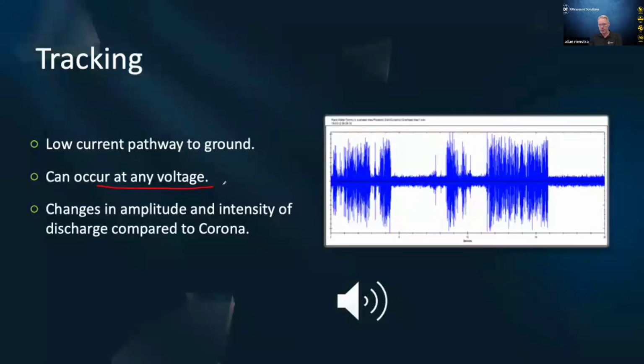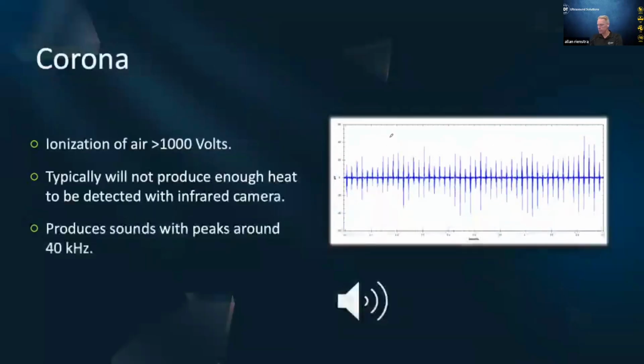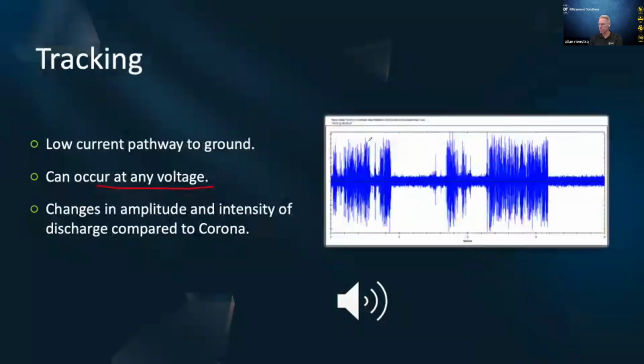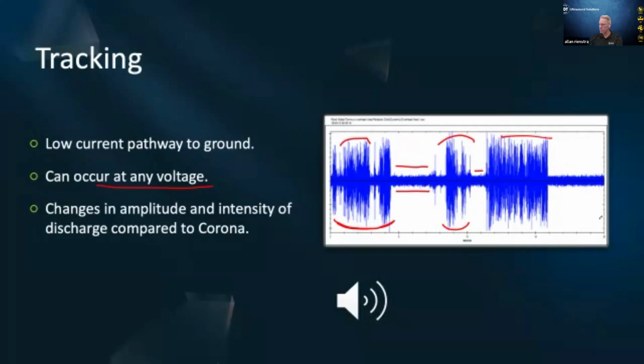The difference between, if we just flip back to the corona, you'll see these repetitive peaks, and they have a repetition frequency. They're all nicely spaced out. Tracking becomes more random. So you'll see short bursts here, then you'll see quiet, and short bursts here and quiet, and then more short bursts. And this is why also thermography on its own doesn't work that well, because in this zone here, you may have some heat generated, but then it goes quiet for a bit and the heat goes away. So depending on when you're doing the scan, you may see heat, you may not see heat. But if you're listening ultrasonically, that's fairly unmistakable.